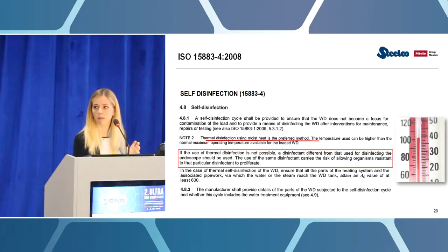But drying is also a very important activity, because some bacteria, the so-called gram-negative bacteria, thrive in wet environments. If humidity is left inside the channels of our endoscopes, it can cause bacteria to reproliferate over time. That's why it's important that all endoscopes are properly dried at the end of the day. This is addressed by a new standard that came out three years ago, regulating drying and storage cabinets for endoscopes.